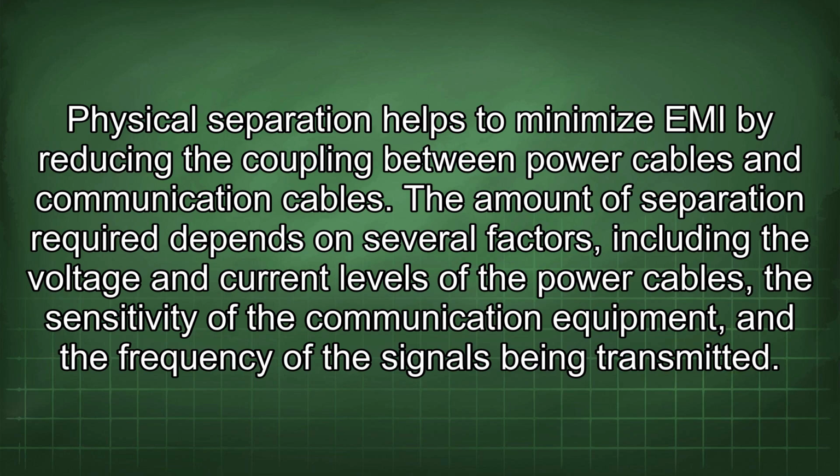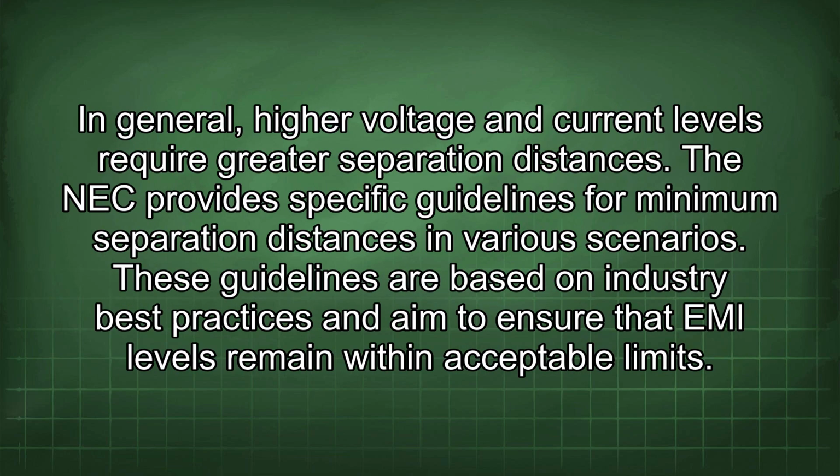The amount of separation required depends on several factors, including the voltage and current levels of the power cables, the sensitivity of the communication equipment, and the frequency of the signals being transmitted. In general, higher voltage and current levels require greater separation distances. The NEC provides specific guidelines for minimum separation distances in various scenarios. These guidelines are based on industry best practices and aim to ensure that EMI levels remain within acceptable limits.